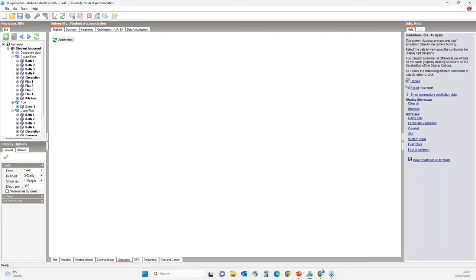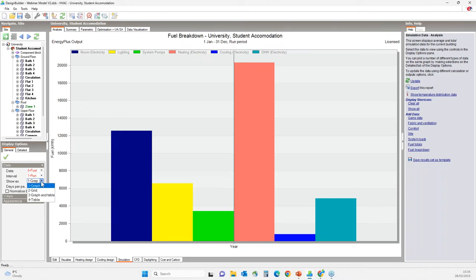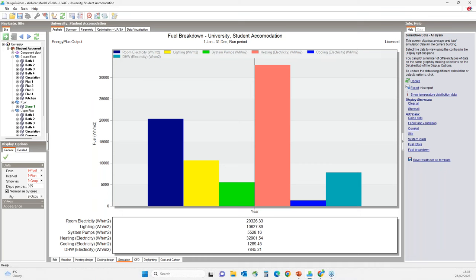It is also good practice to do proper QA checks to your model before you embark on these final runs. You can do this by simulating short time periods at high time frequency like hourly or sub-hourly levels to ensure that the systems and operations are running as they should. This type of sanity checking is essential and good practice in modeling. I will look at the fuel breakdown at run period levels and look at graph and table normalized by area.